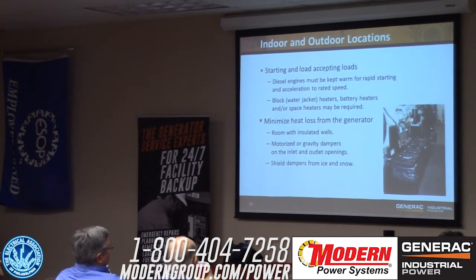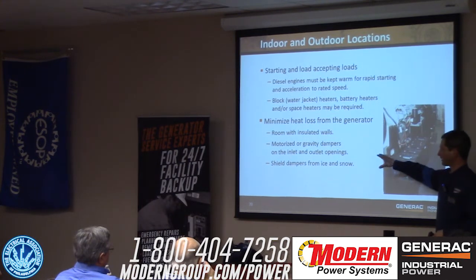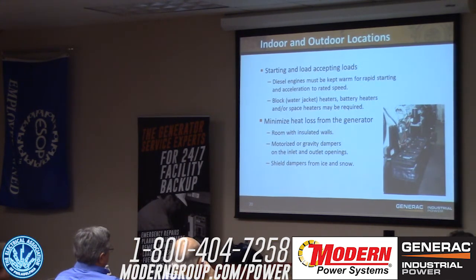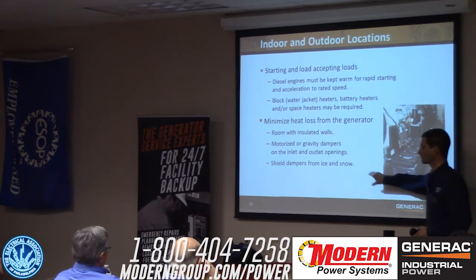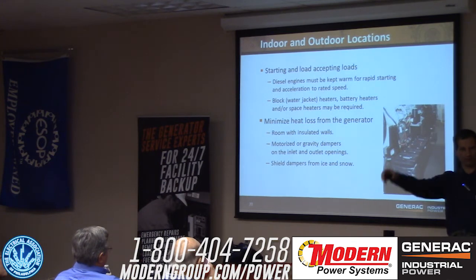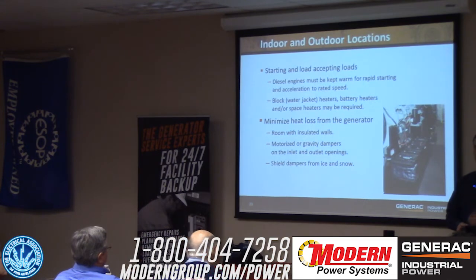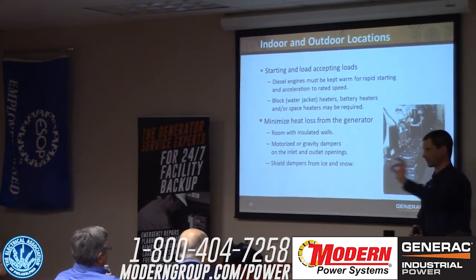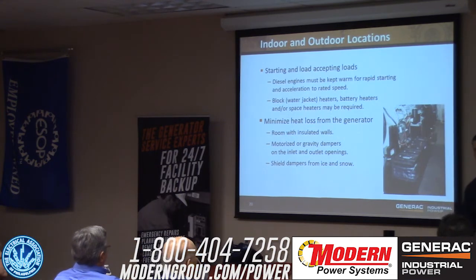So now, these are kind of common no matter where the generator is located, inside or outside. We already mentioned that the diesel's got to be kept warm, block heaters, jacket heaters, etc. We're going to minimize the heat loss from the genset itself. I could do motorized or gravity dampers on the intake or the exhaust. In extremely cold locations, you may want to do that. But if that is a requirement, make sure they don't freeze up. So you're going to have to put some type of shield over them so they don't get iced. And in some extreme environments, they'll even heat those things. They'll even put like strip heaters on those louvers so that they don't ice up.